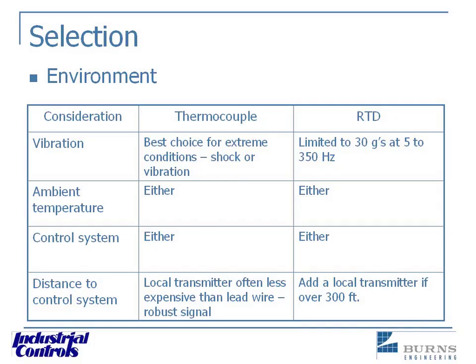But an interesting note is you really should get that transmitter away from the head of the RTD or the thermocouple. Get it away from that heat source if you can. The transmitter is an electronic device. So once removed from the heat source, it's extremely helpful and handy. You can recalibrate it. It's worth the investment. Right. Most of those have about an 80 or 85 degree C maximum ambient temperature limit on them. Yeah. And it can affect accuracy if you're at anything other than room temperature.